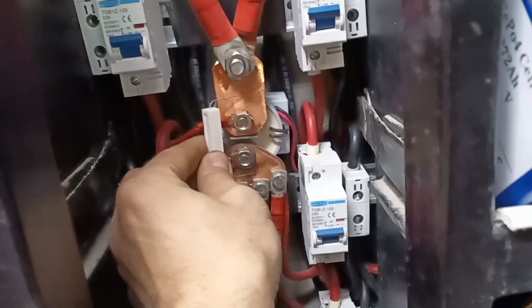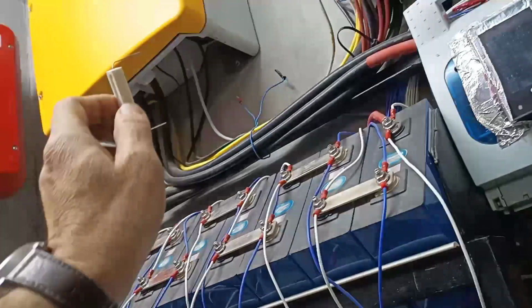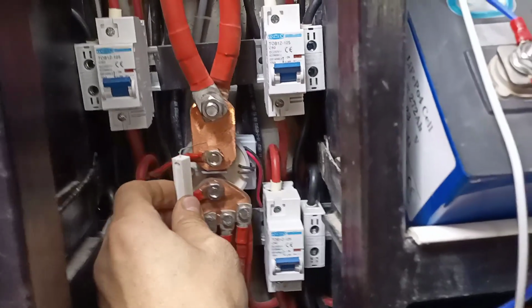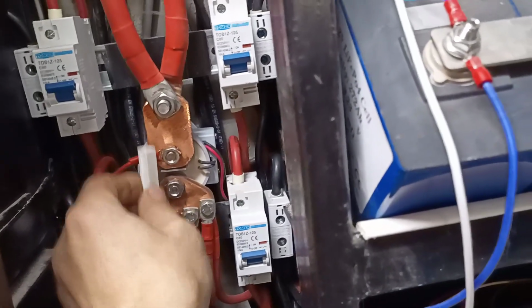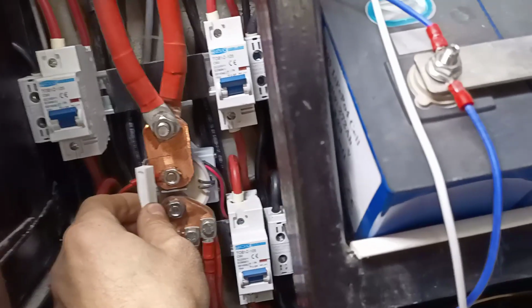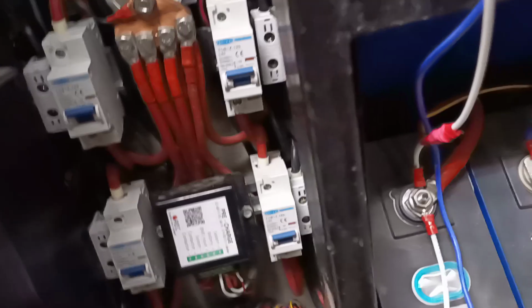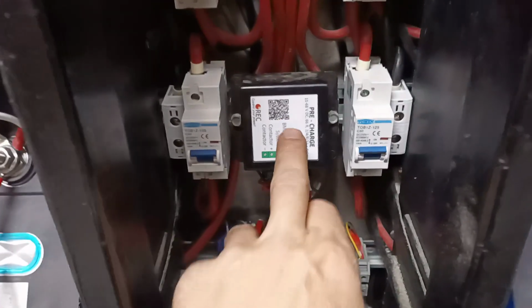The procedure will be: I short the contactor to send electricity to the SMA inverter, and when I'm sure—after keeping it for some time—that the capacitors are pre-charged, only then will I start the BMS, to make sure the contactor doesn't weld. So I advise you not to trust this pre-charge unit, and to manually pre-charge your inverter instead.